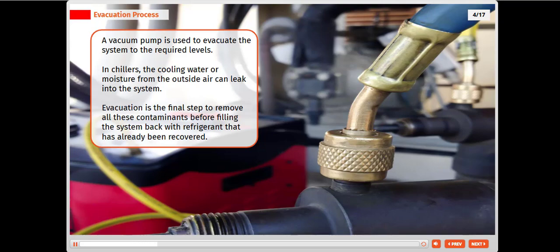In chillers, the cooling water or moisture from the outside air can leak into the system. Evacuation is the final step to remove all these contaminants before filling the system back with refrigerant that has already been recovered.